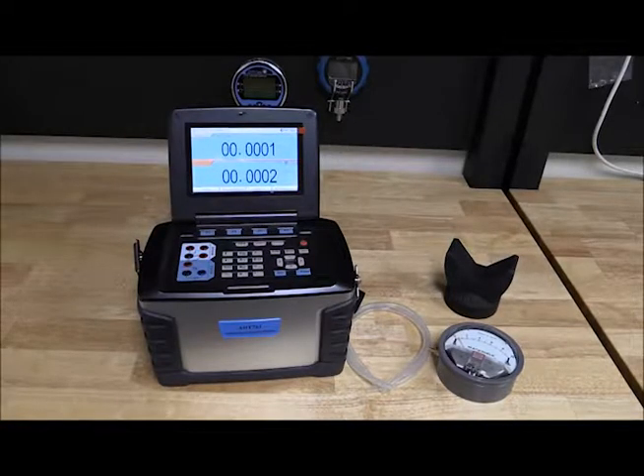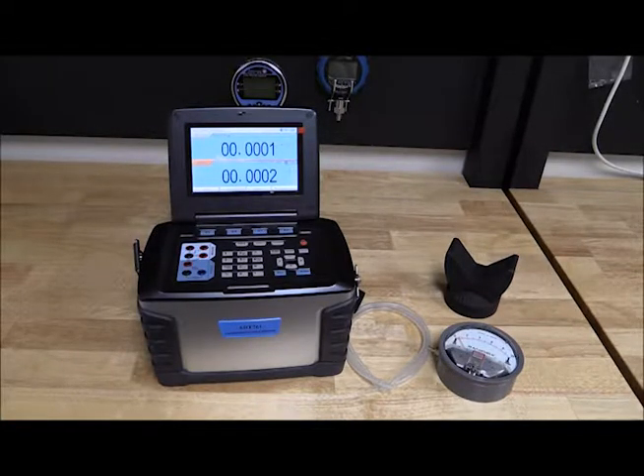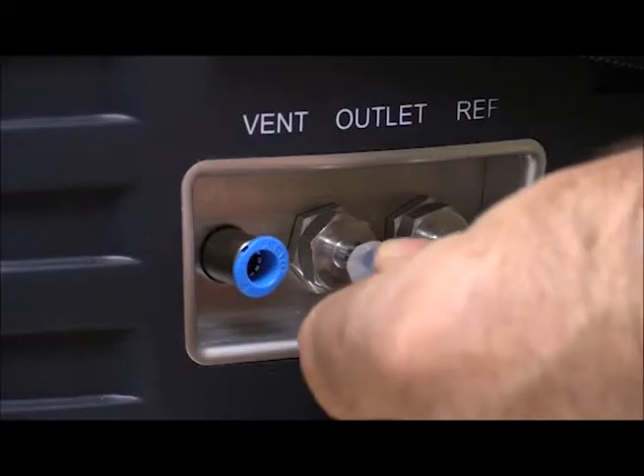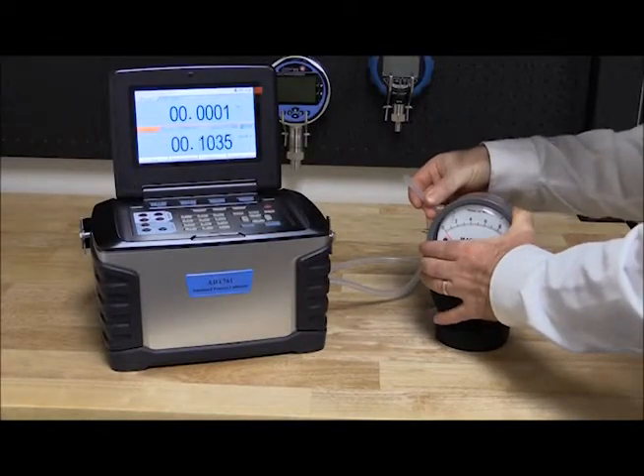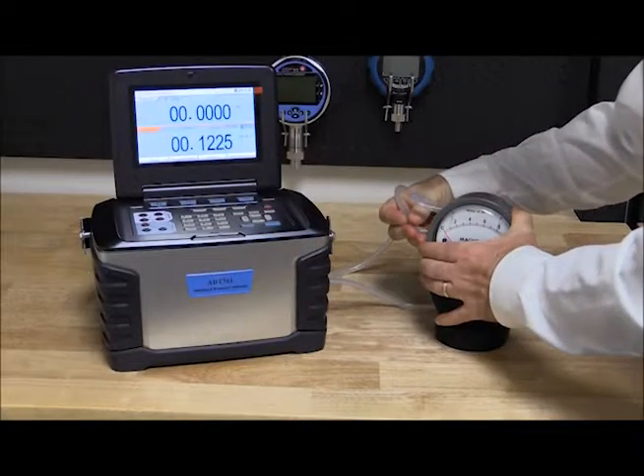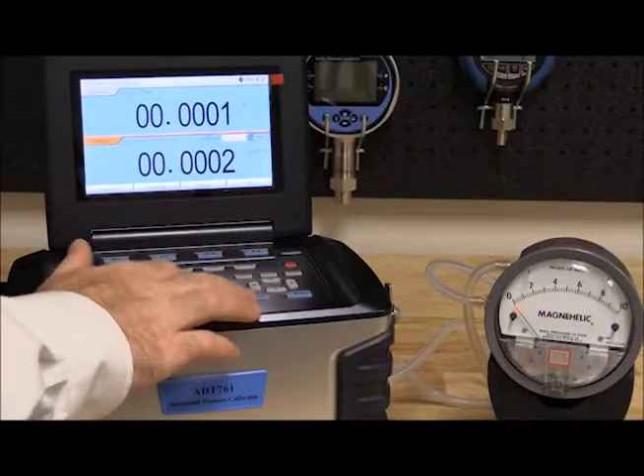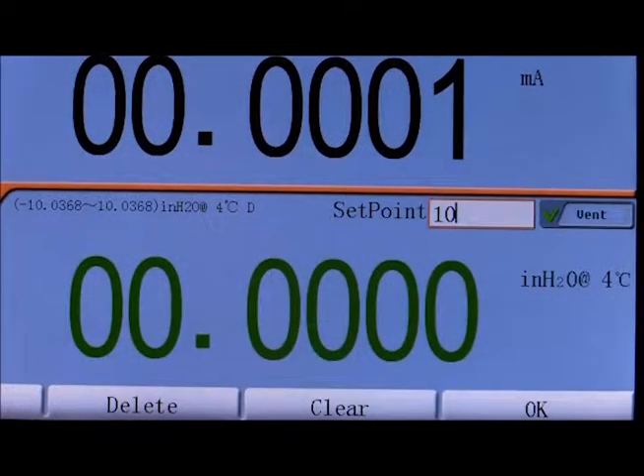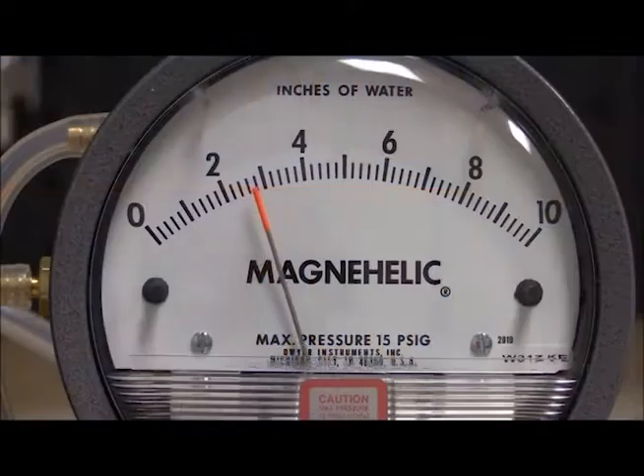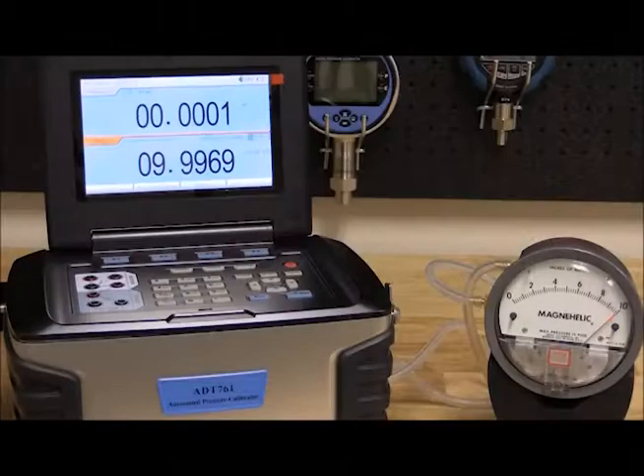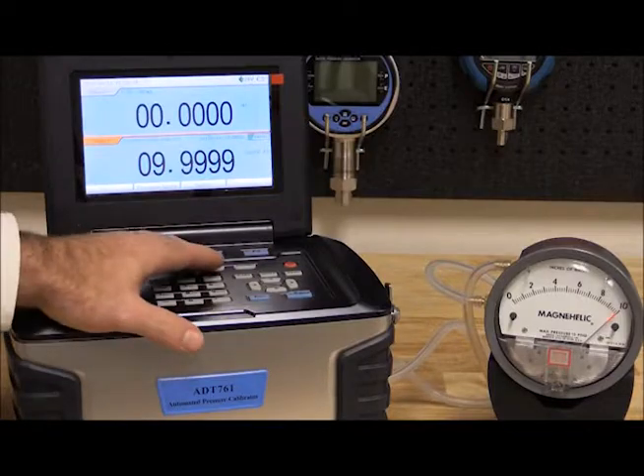For this example, we use an Additel 761 LLP automated pressure calibrator as our pressure source and reference. We will be calibrating a Magnehelic differential gauge that is 0 to 10 inches of water. The outlet port of the 761 is connected to the high port of the DUT. Then the reference port of the 761 is connected to the low port of the gauge. To exercise the gauge, simply enter the full scale pressure and press enter. The 761 will supply pressure through a built-in pump and control to the full scale. To decrease the pressure, simply press vent.